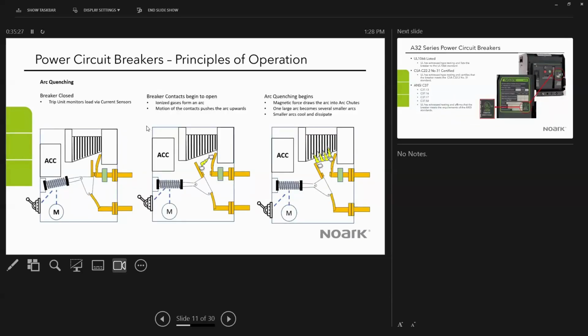Another important part of the operation of a breaker is the arc quenching capability of the breaker. So if you look at the image on the left-hand side, the breaker's closed, it's operating normally. And then a fault happens and the trip unit senses the current is rising and it signals the breaker to open. And when the breaker opens, as the contacts begin to separate, ionized gases form an arc between the two contacts. And that's typically a bad thing because those arcs are what deliver the heat and explosive energy that comes with a fault.